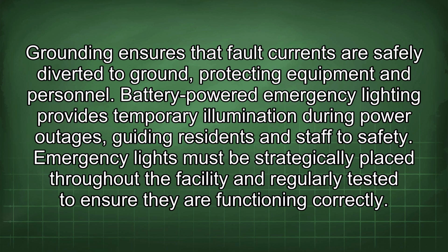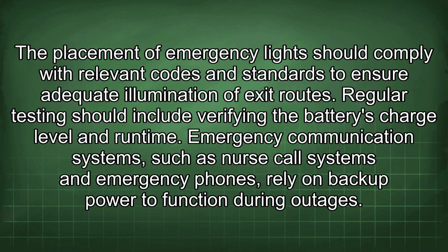protecting equipment and personnel. Battery-powered emergency lighting provides temporary illumination during power outages, guiding residents and staff to safety. Emergency lights must be strategically placed throughout the facility and regularly tested to ensure they are functioning correctly. The placement of emergency lights should comply with relevant codes and standards to ensure adequate illumination of exit routes. Regular testing should include verifying the battery's charge level and runtime.